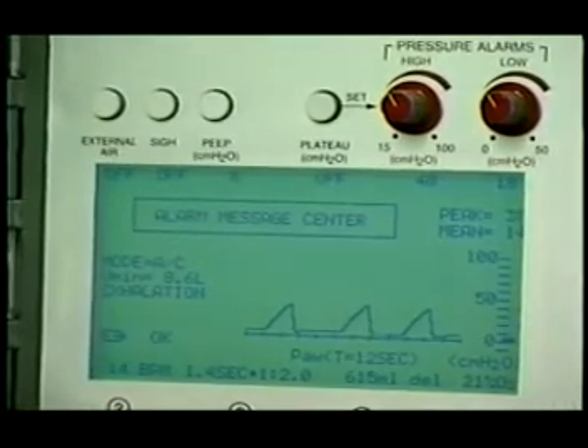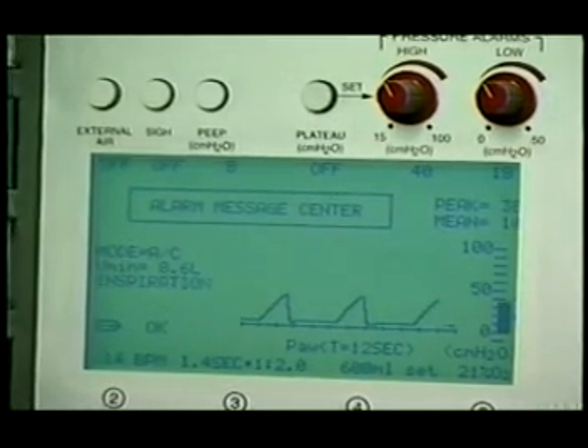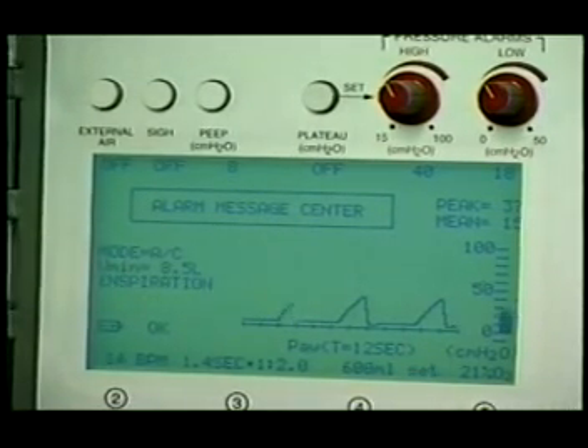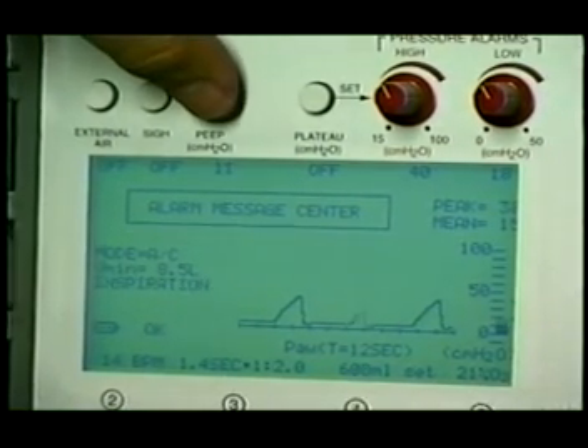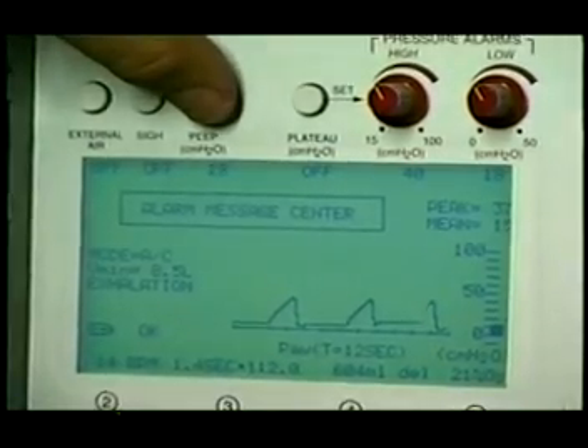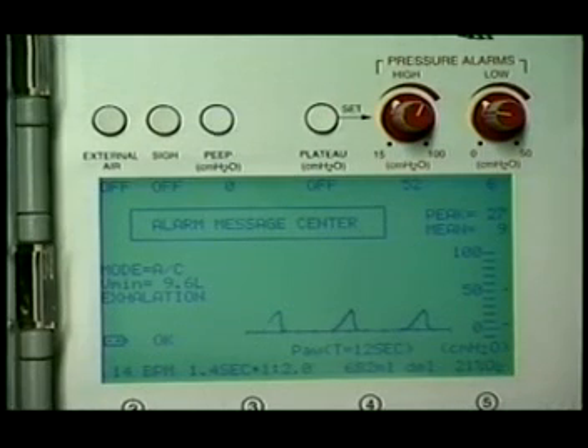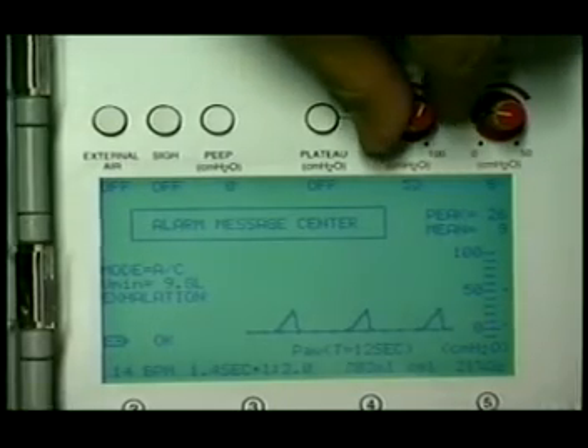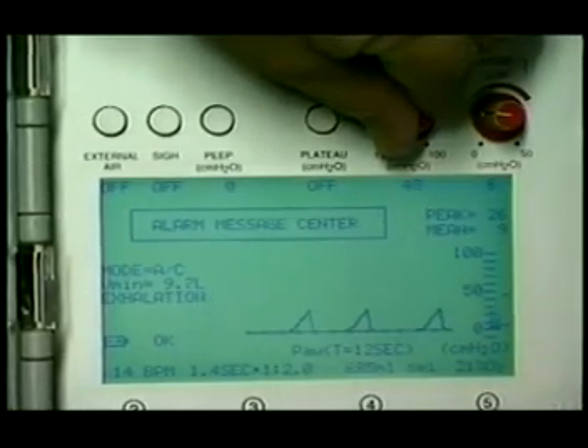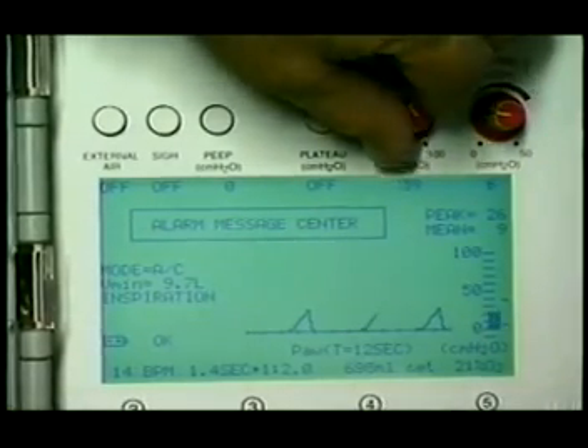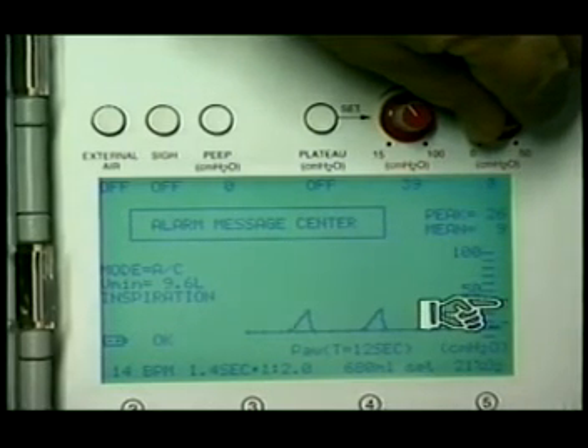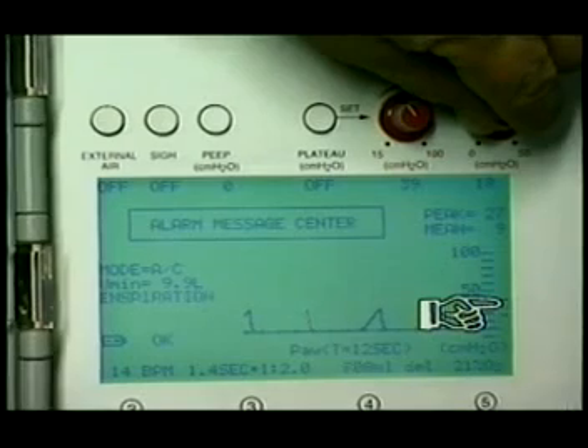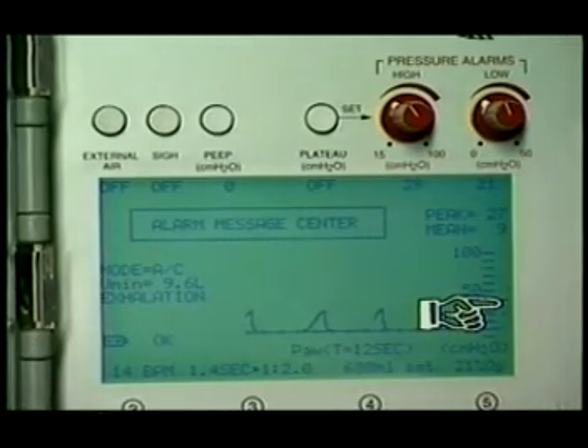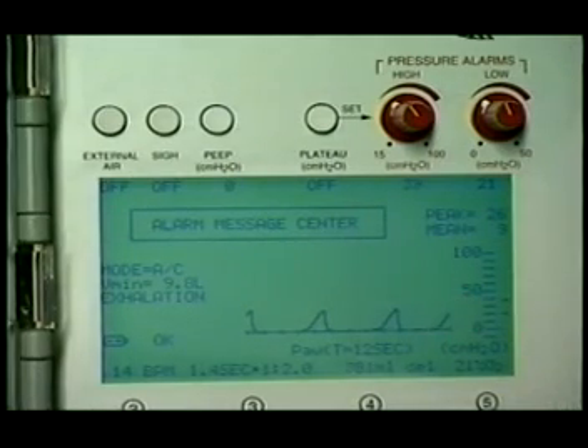Do not attach an external PEEP valve. PEEP is generated internally using software control of hardware. To eliminate PEEP, repeatedly press the push button switch. PEEP is adjustable to 20 centimeters of water, then returns to 0. The low and high pressure alarm limits can be quickly set. First, make note of the peak airway pressure displayed above the digital bar graph. Next, set the low and high airway pressure alarm controls to values lower and higher than the displayed peak airway pressure. Another way to set the alarm limits is by observing the digital bar graph. 2 small bars or ticks appear to its right. These ticks correspond to the current low and high airway pressure alarm control set points and move upwards or downwards as their respective control is turned.